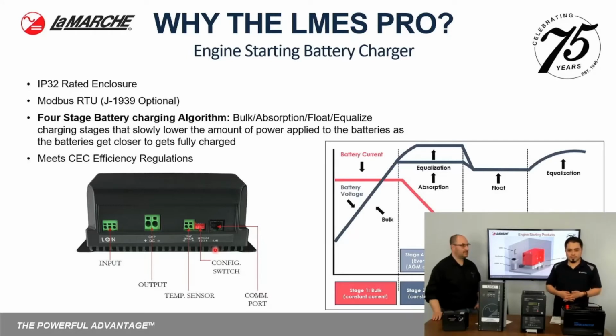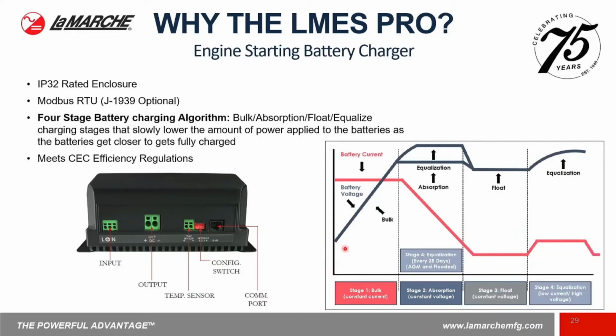There is also a 4-stage battery charging algorithm on this charger. It gives you the bulk stage here. As you can see, you get a constant current where you have that lower voltage, or you're starting to charge your battery. And when you come up to a voltage, you then go into the absorption rate or your equalize rate, depending on the configuration. You will then, at that time of your equalize or absorption, move into your float. As you can see, your current has already dropped down into a trickle current or a float current. And then stage 4 is where you would go into your second equalize stage as well.